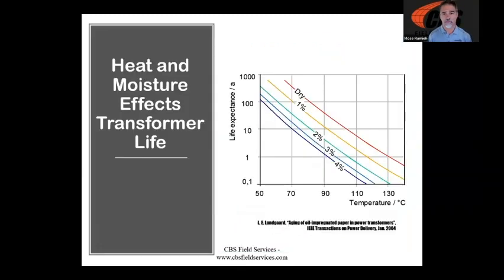And like I say, I mentioned earlier about keeping our transformers cool. Well, we'll also point out that if we keep them dry, we can expect to have a longer life. So a transformer that's operating at 4% moisture at 70 degrees C has about a 10-year life expectancy, right? A transformer that is operating at 1% moisture at 70 degrees C, we can expect to have about a 100-year life expectancy. So once again, keeping our transformers cool and dry is of the utmost importance.